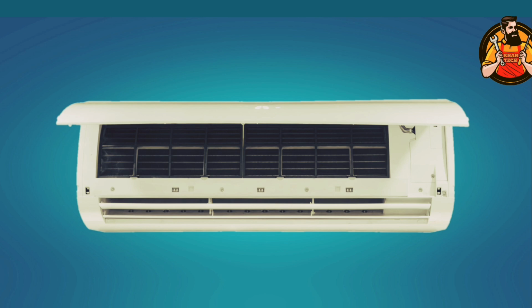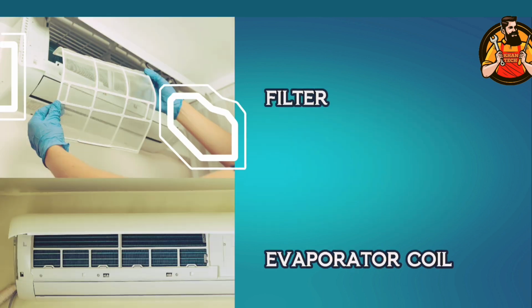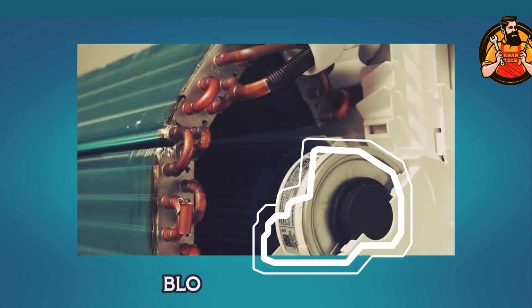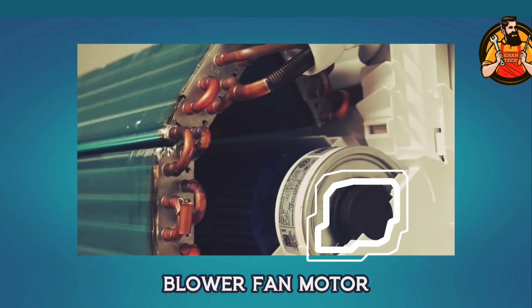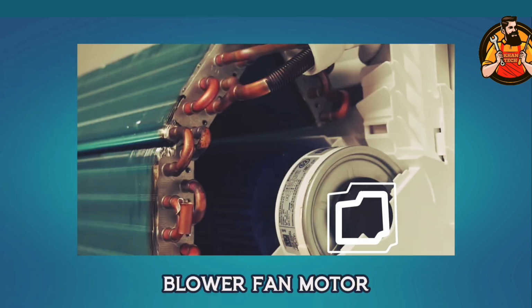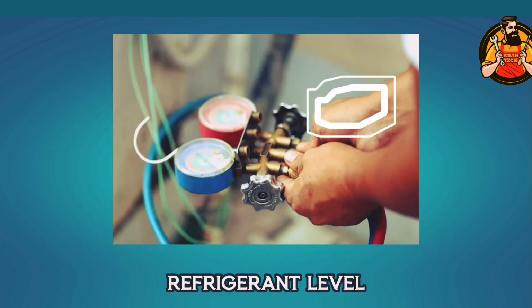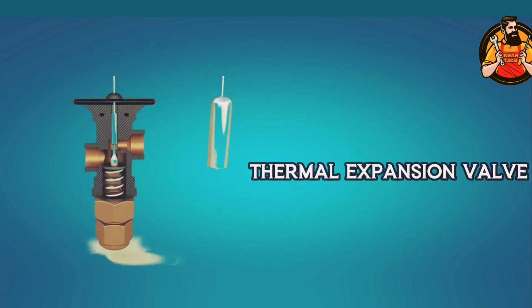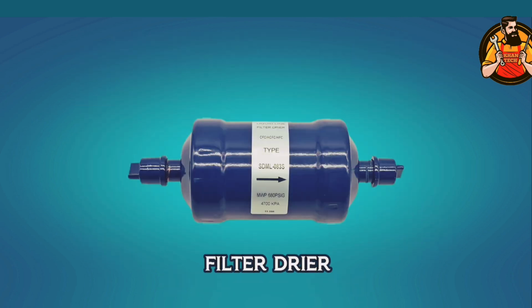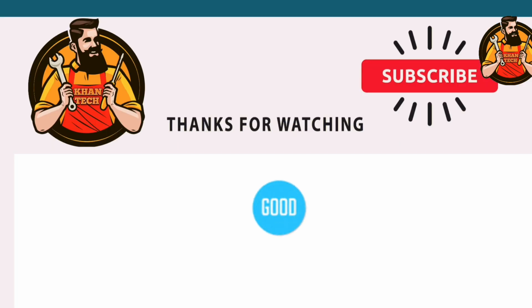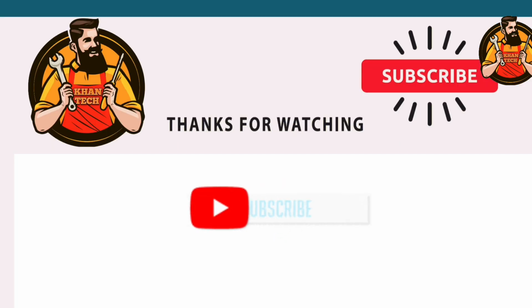After the ice melts, check if there is any block in the filter and evaporator coil. Then check if the blower fan motor is working. After that, check the refrigerant level, thermal expansion valve, and filter dryer. This problem can be solved by fixing any equipment that is not working properly. We can see how to find and fix each equipment problem in the following videos.